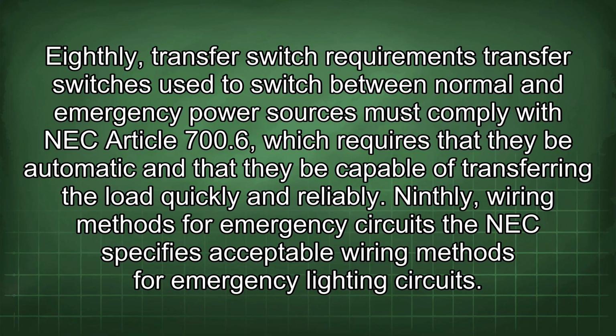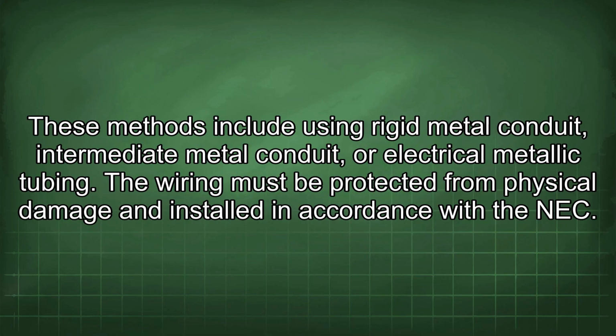The NEC specifies acceptable wiring methods for emergency lighting circuits. These methods include using rigid metal conduit, intermediate metal conduit, or electrical metallic tubing. The wiring must be protected from physical damage and installed in accordance with the NEC.